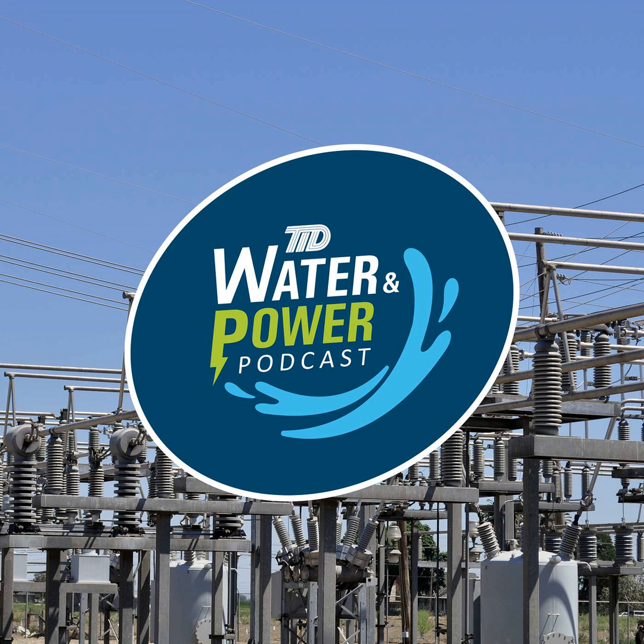We're going to have, for sure, voltage transformers out there. We have instrument transformers, and usually that's in the form of a voltage transformer as well as current transformers. The voltage transformers will attach to the bus and sense what is actually the voltage that is sensed there, and that's transformed down to be used by our protective relays. We also have current transformers, which are usually part of the circuit breaker, actually, and that's sensing the current that's either coming in or leaving on that breaker, and again, is brought into our protection system. Okay. And so with that information, not only does it provide cues for our protection system to respond to, but it's also providing system information for our power control center to monitor.